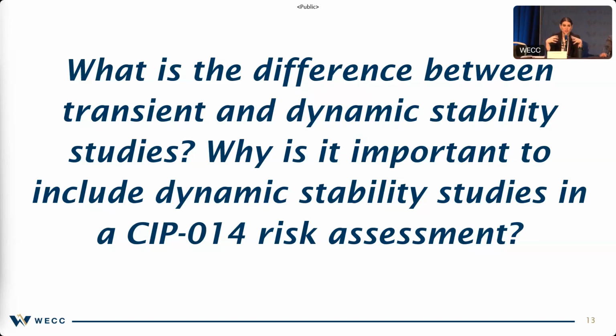You may end up in situations where these are computationally excessive and you're not able to study a wider area — you're looking at very localized impacts. Dynamic is a little different. It's looking over a longer period of time, whereas transient may be looking at individual cycles. Dynamics could go from cycles to seconds to maybe half a minute, where you're looking at how nearby controllers and protection systems are responding, whether they're going to respond appropriately, and whether things are going to be stable.